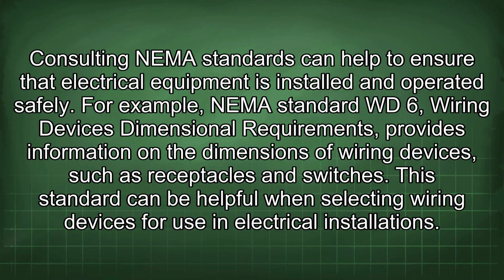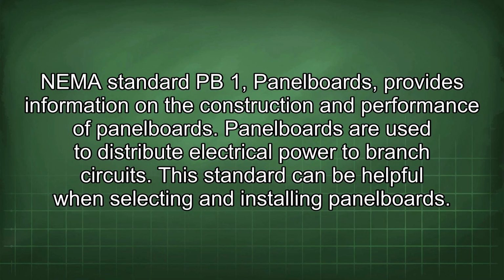For example, NEMA Standard WD6, Wiring Devices Dimensional Requirements, provides information on the dimensions of wiring devices such as receptacles and switches. This standard can be helpful when selecting wiring devices for use in electrical installations. NEMA Standard PB1, Panelboards, provides information on the construction and performance of panelboards. Panelboards are used to distribute electrical power to branch circuits.